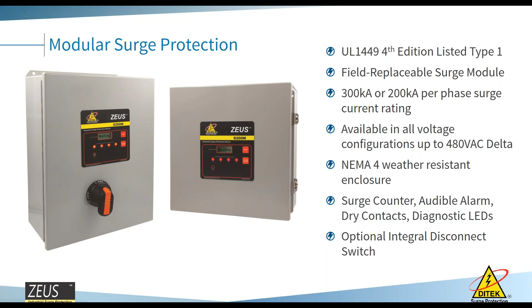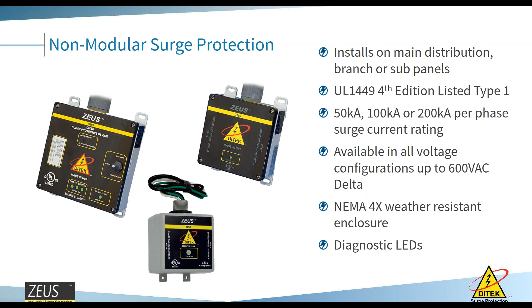We also have non-modular. Again, you could still put these on your main service, or you can put these on a different panel board. These devices do not have a replaceable brick. Like these devices, you would open these, you could replace the brick inside, but they have a higher cost for that. These devices, once they do self-sacrifice, like the D200, it'll take 200,000 amps for that device to self-sacrifice. It also has dry contacts and an audible alarm. We also have a D100 and a D50. D50 is probably our entry-level light commercial, high-end residential protector. We sell, I probably couldn't even quantify, it's probably one of our best sellers in the electrical space.